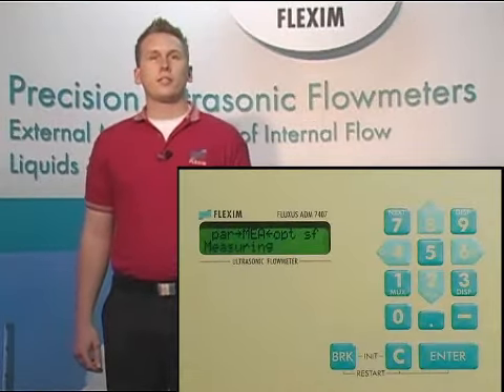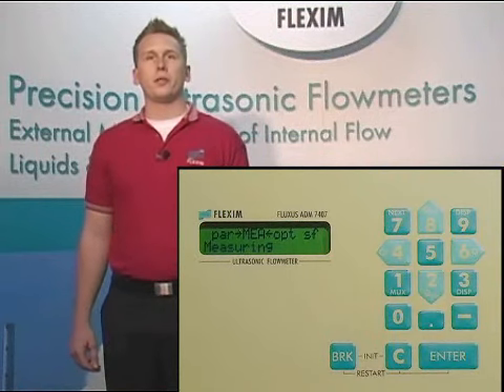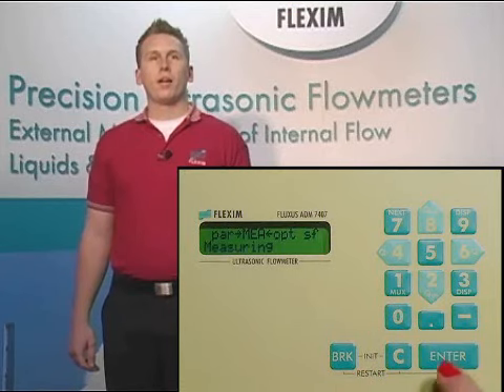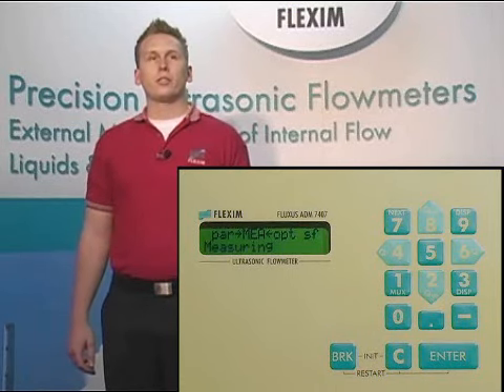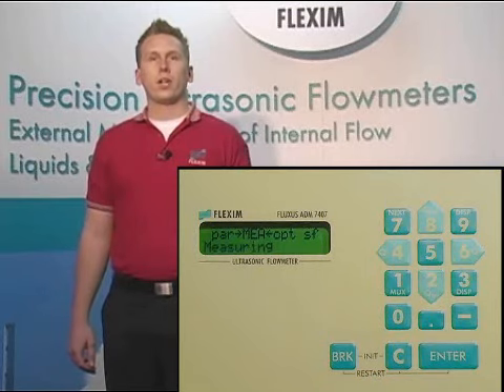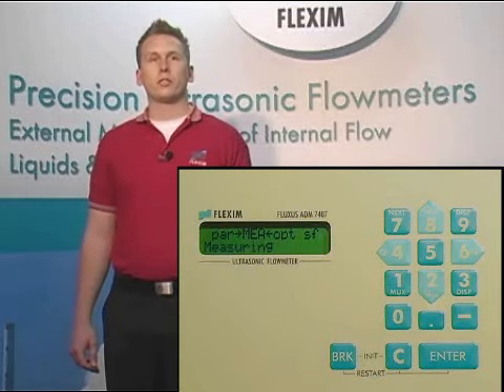Let's turn our attention now to the keypad of the 7X07 BTU meter. We have a clear button, an escape or break button, and an enter key on the right side of the keypad. The clear button allows you to clear values you've entered incorrectly. The break button allows you to escape back to the main menu while navigating anywhere within the menu system. And of course, we use the enter key to confirm all of our choices and to navigate deeper into each menu.